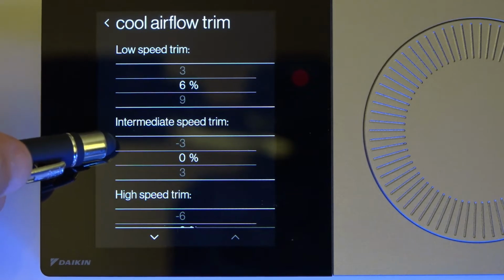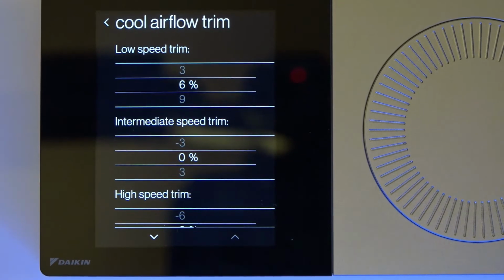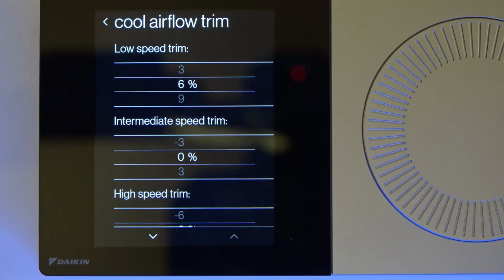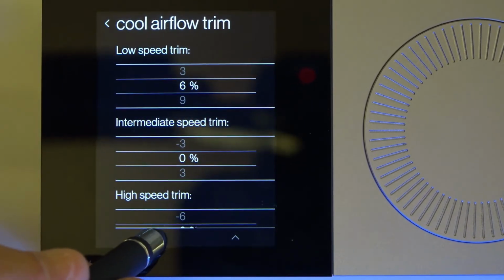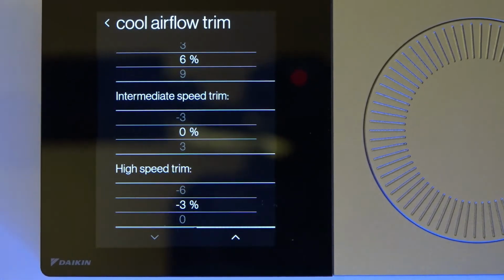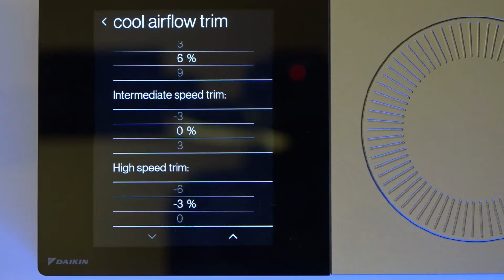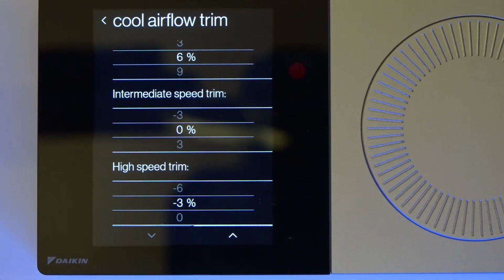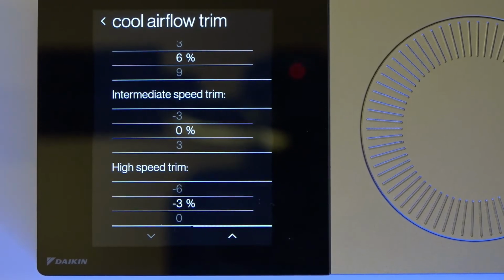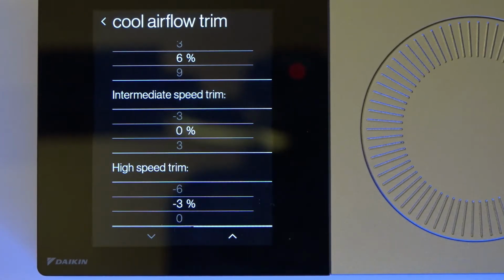In the intermediate trim speed, I just leave that alone. I have really good success without having to change that at all. So I just leave it. Scroll down a little bit here. Under the high speed, I give it a 3% or 5% deduct in CFM. So when it's 95 outside, the machine's loaded up and running, I drop my fan speed. I do a little bit better on my coil temperature, maybe 1 degree colder with this. I do a better job of dehumidification with a colder coil, and since my coil is super saturated, I've slowed my airspeed down, so that also helps me with my static pressure.